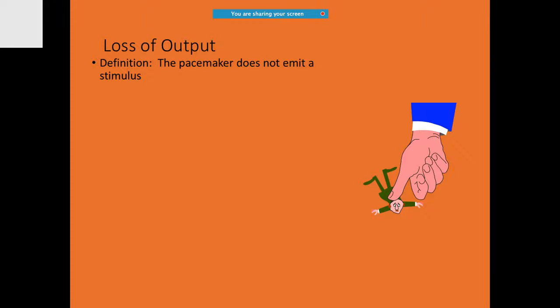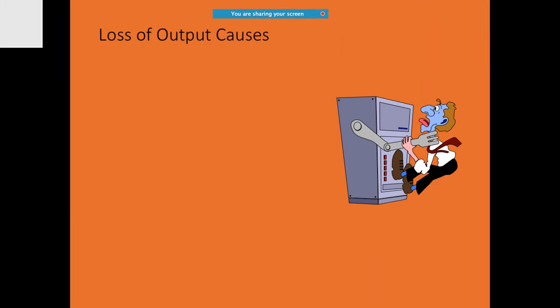Loss of output is when the pacemaker does not emit any output at all. You can see in other beats there is a clear unipolar pacing spike causing good ventricular capture, but in between — in the area marked with a red circle — there should have been a pacing stimulus but no pacing spike is seen. Causes include: a loose screw, lead fracture, pacemaker inhibition, concealed stimulus on the ECG, or battery depletion.